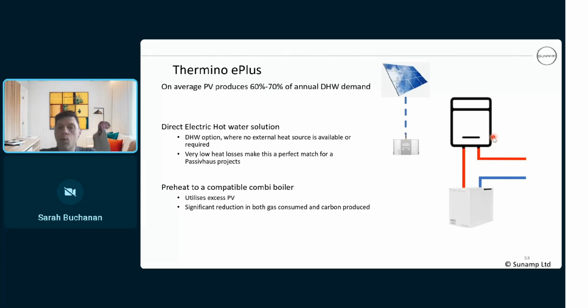So the one thing you've got to remember is what's the boiler manufacturer's maximum inlet temperature allowance. That can range from manufacturer to manufacturer - I think Alpha is 65 or plus that. The new Worcesters are up to 65 degrees.